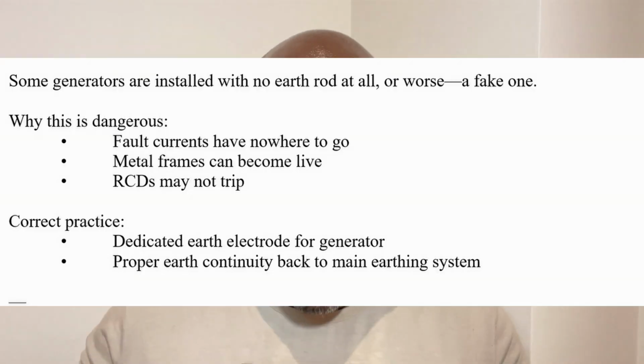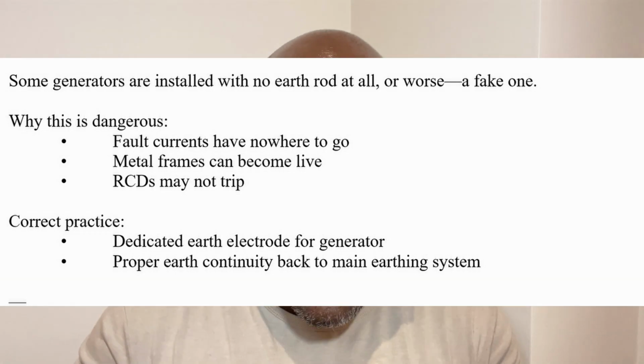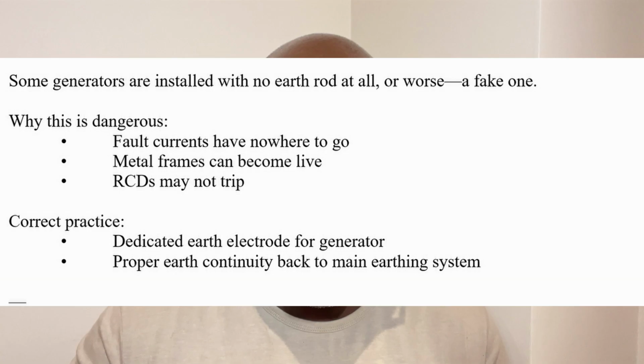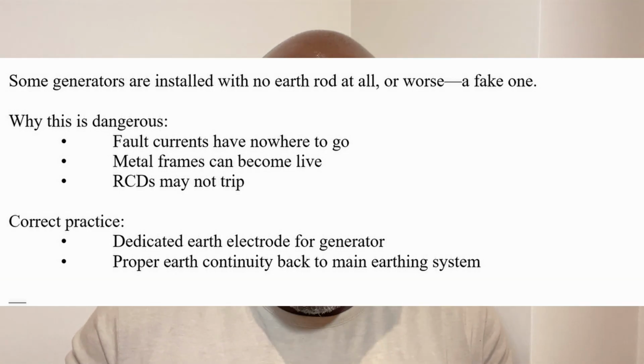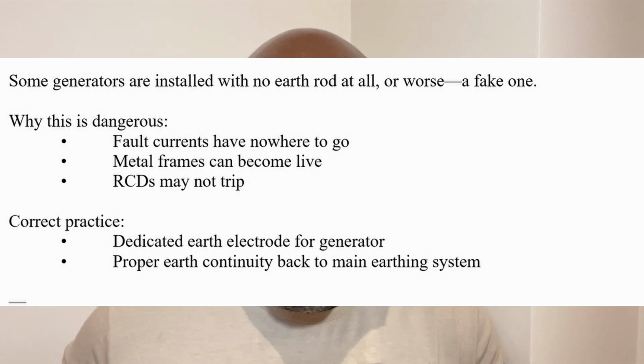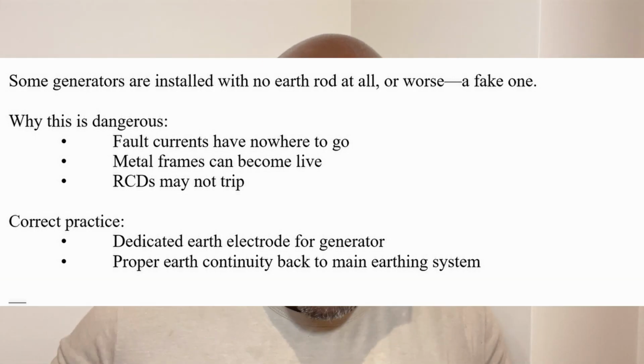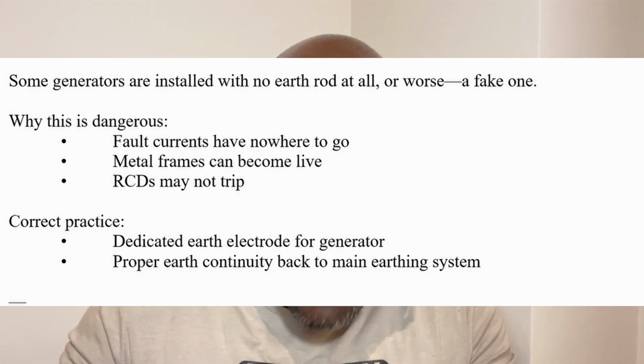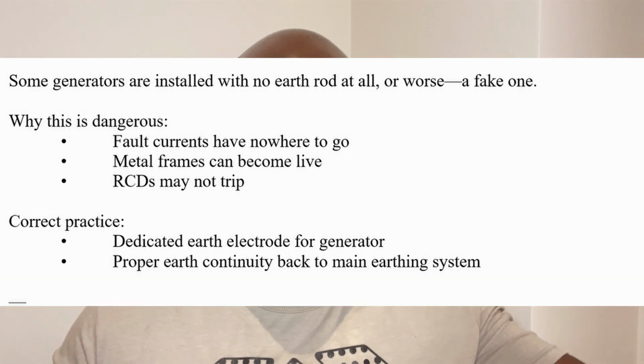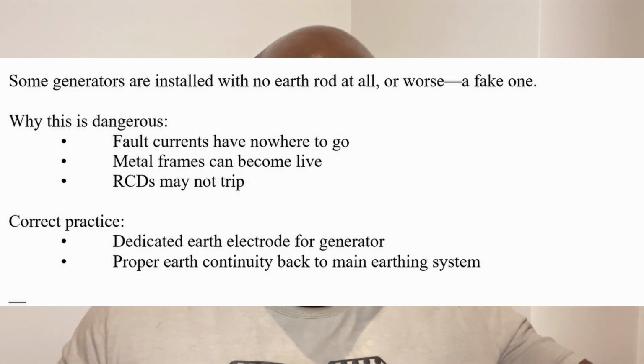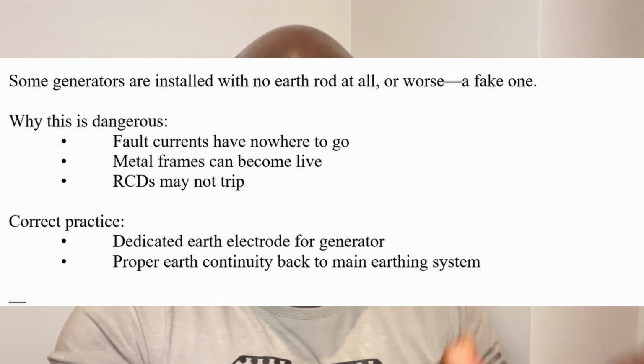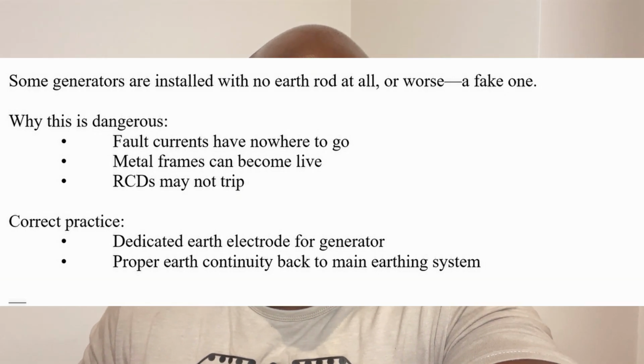No earthing or fake earthing. Some generators are installed with no earth rod at all, or worse, a fake one. Why is this dangerous? Fault currents have nowhere to go. Metallic frames can become live, electric shock to people. The RCD may not trip. What is the correct practice? You must have a dedicated earth electrode for the generator. Then also have proper earth continuity back to the main earthing system. So when I was talking in my previous video about integrated earthing, foundational earthing, if you haven't watched that, click up here. You would take an earth tail from that foundational earthing to the generator earth rod or to the generator earth connection point. So the generator has its own independent earth connection. That is the best practice.